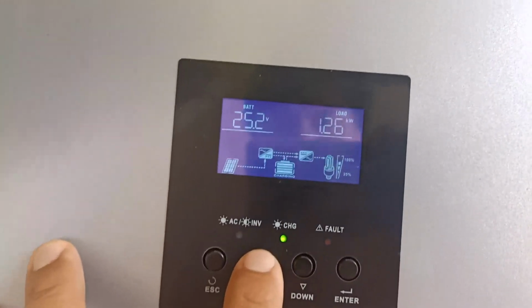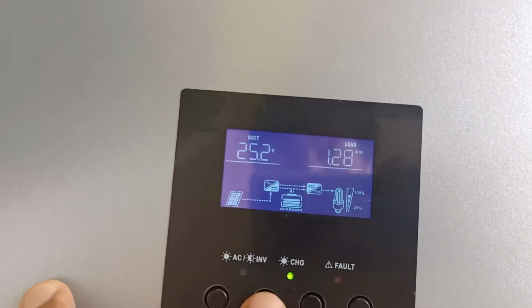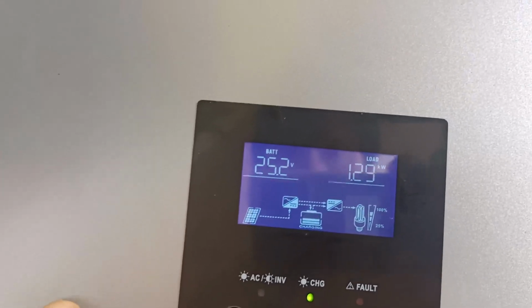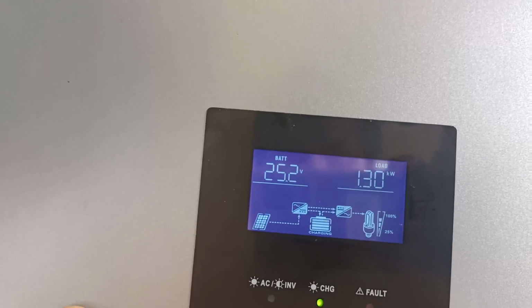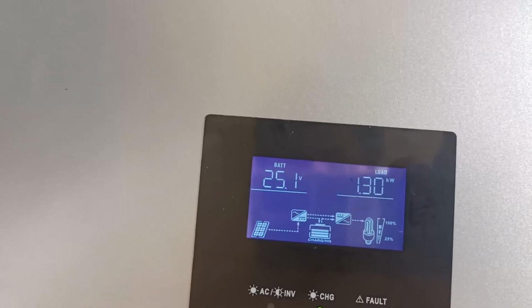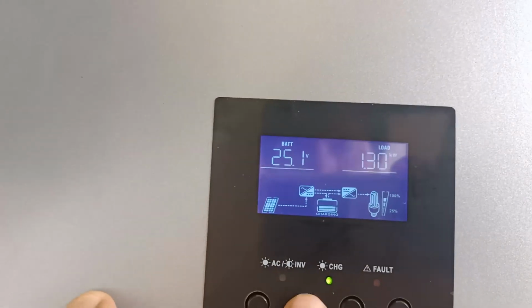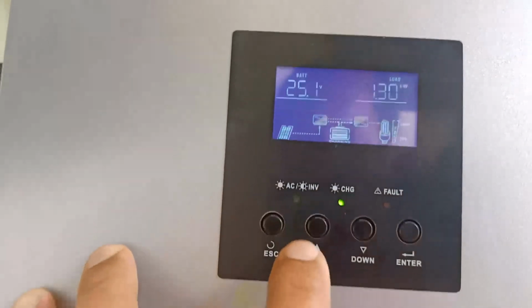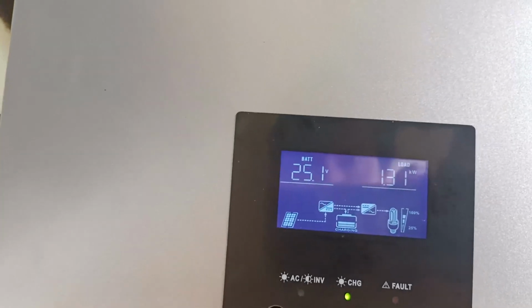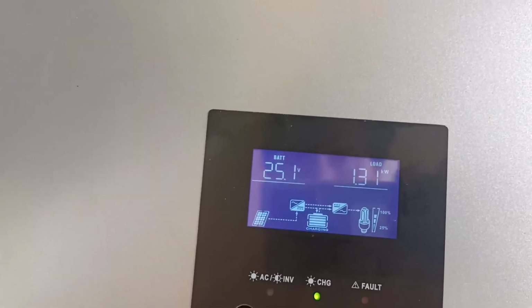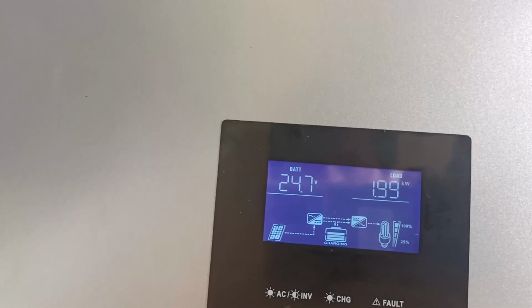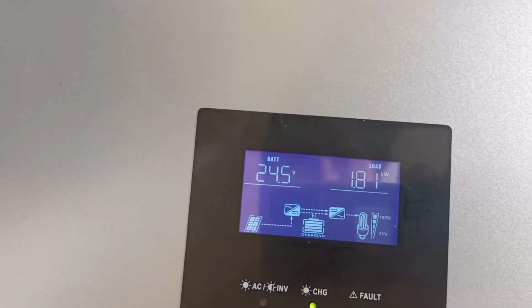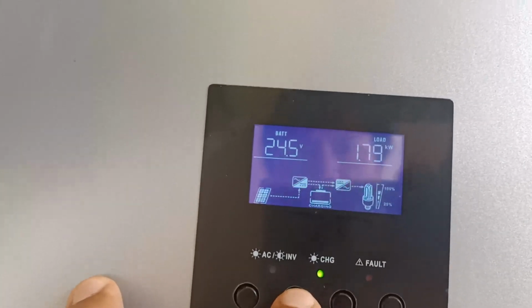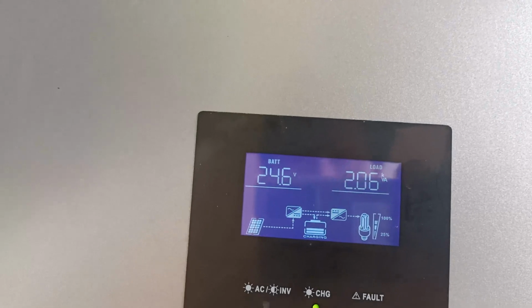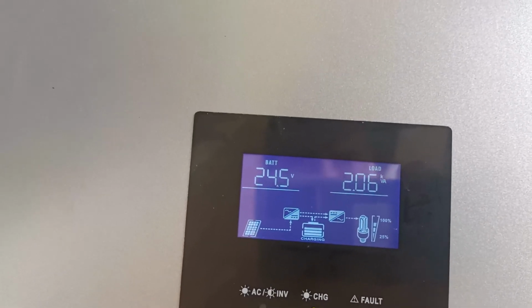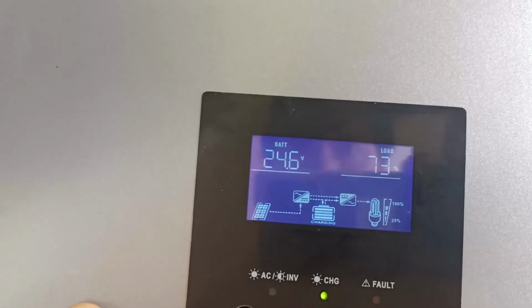So the third aircon will be on shortly, and it should go up to 1.6 kilowatts. So there's a message here telling me the overload, and the overload is brief because it needs to warn people. Okay, there's the overload. Now it is at 1.8. So it is now at 2 kVA. So there's one more 1000 VA left. And the load is at 73%.